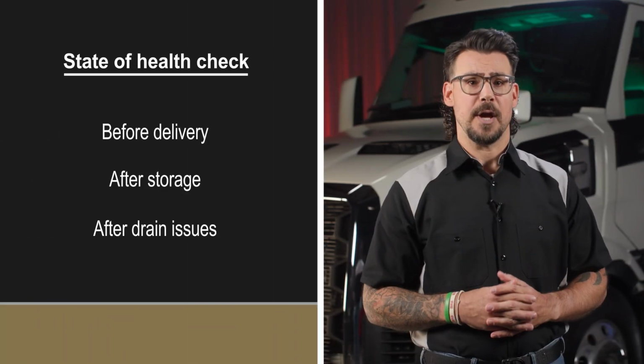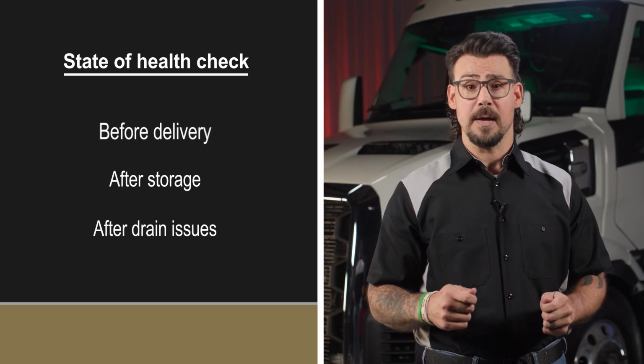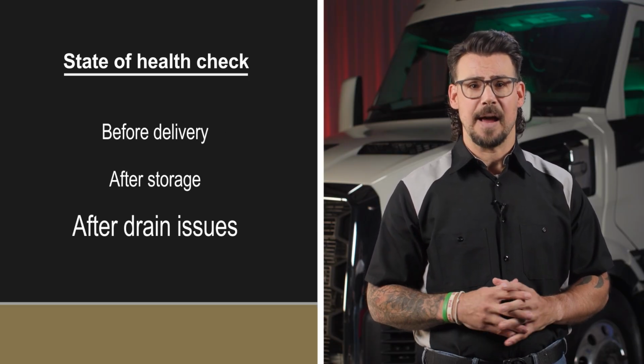There's also a critical rule. When batteries are connected in series, their state of health and cold cranking amps must be equal. Never mix old batteries with new batteries. That mismatch leads to uneven charging, shortened lifespan, and even pack failure. State of health checks should always be done before delivery, after storage, and any time there's a persistent drain or charging issue.